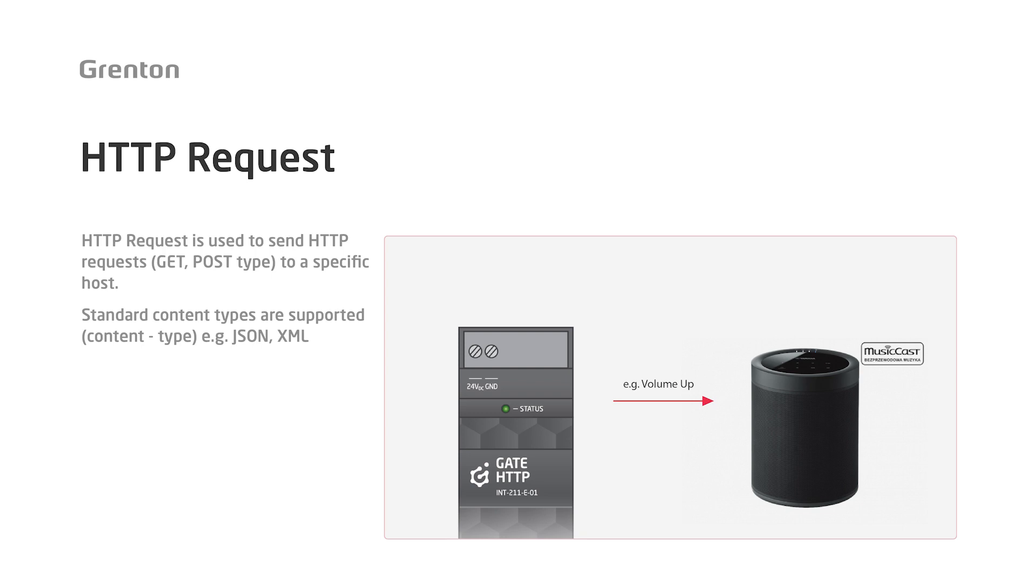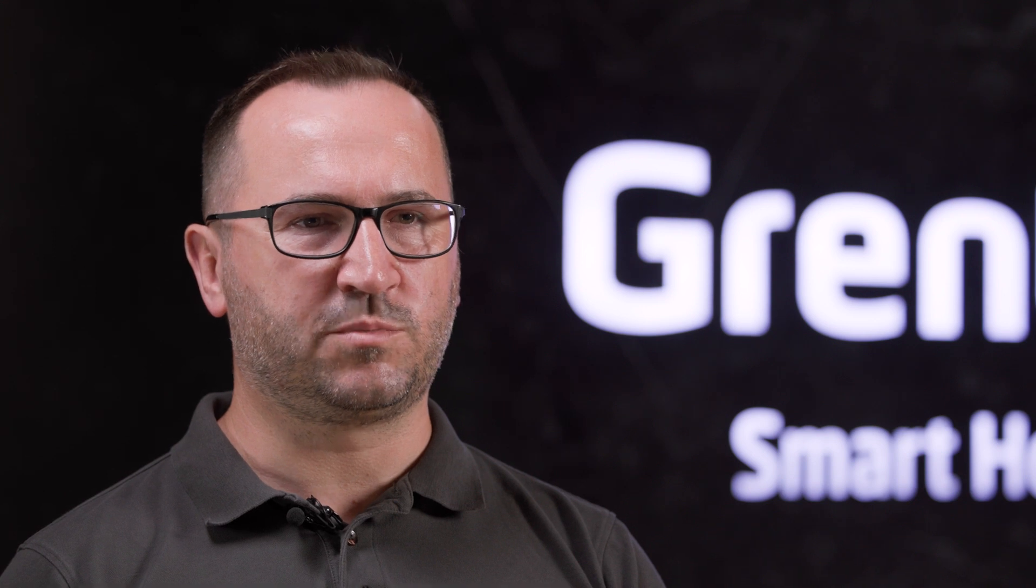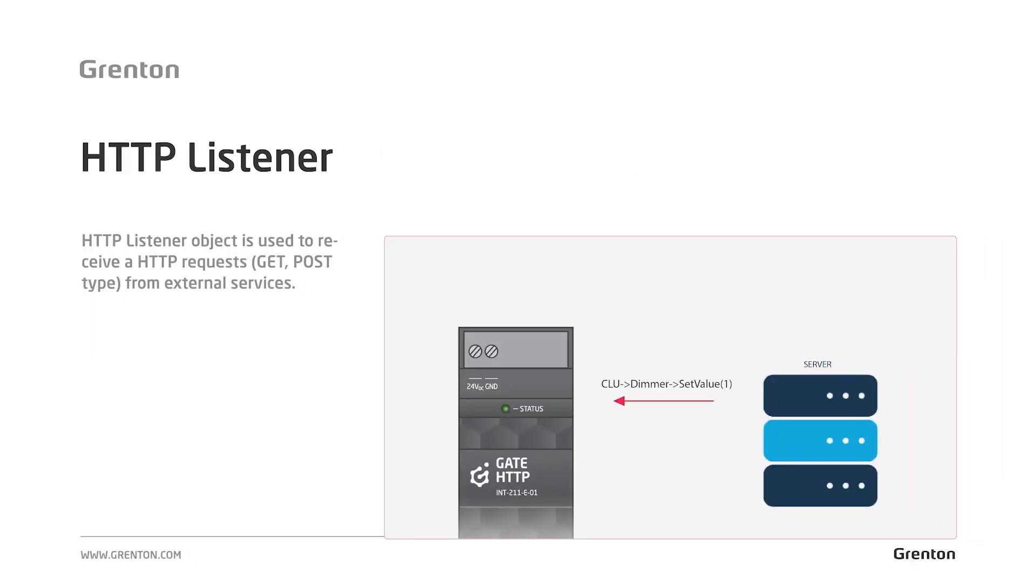This object will be used to send standard POST or GET queries in JSON or XML format. On the other hand, if we want an external device or an external server to be able to download some values from our system, for example information about the read temperature, we will use an HTTP Listener type virtual object, because in our system you will not find such a thing as a ready API. You will create this API yourselves within the configuration. The system is open enough to allow you to access practically any value contained in it, and you will create the query structure yourself.